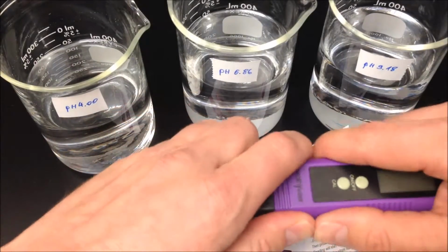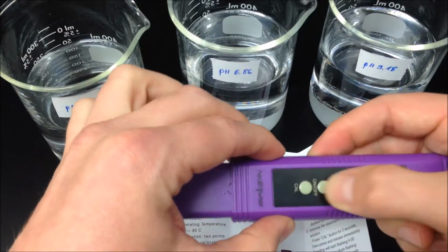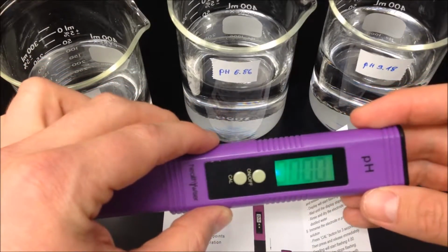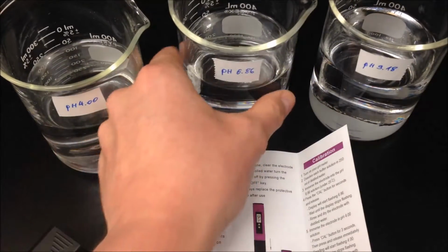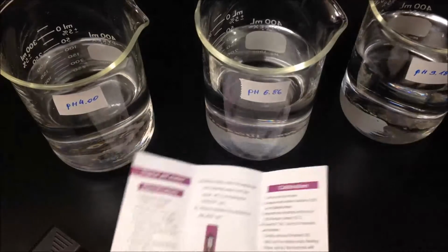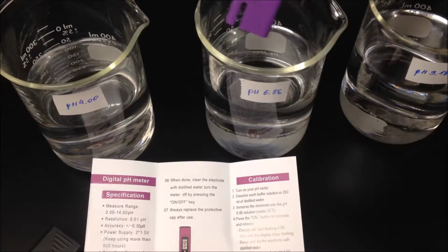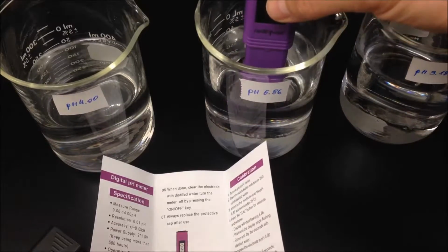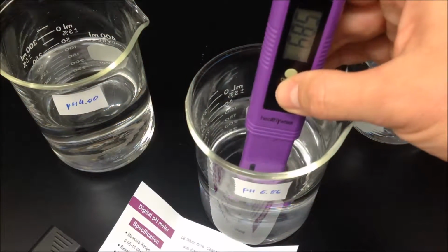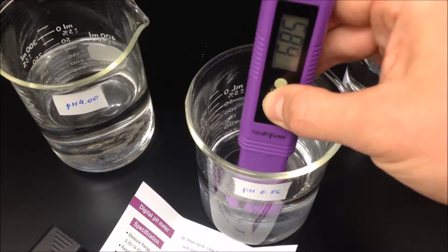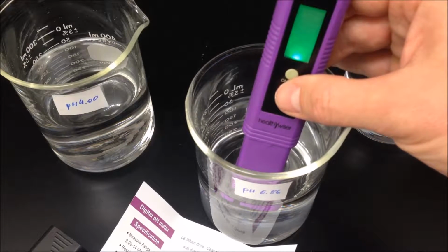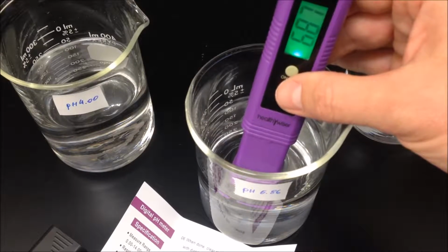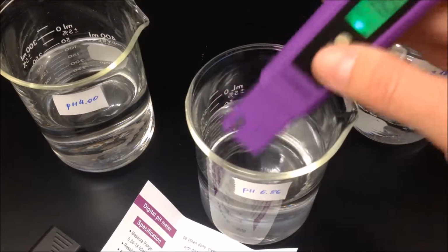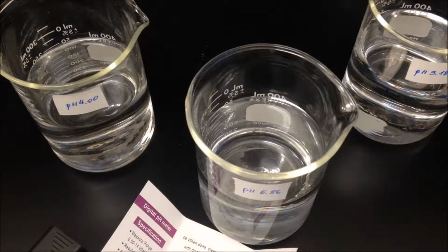So we take our pH meter and I turn it on. I'll be careful. You can see it's a nice digital display in green. Alright, and I'll put it in our first buffer solution. So let's take, as it says in the calibration manual, put it into the solution of 6.86. And maybe I'll pull this a little bit further. And then you push the calibration button for 3 seconds, in this case, and then you release it, and it should blink. There you can see, or flash. And when it stops flashing, it's done. Alright, so what I do now is I just wash it quickly with distilled water, because you don't want to have any pH 6.8 buffer in your other buffer solution, right?